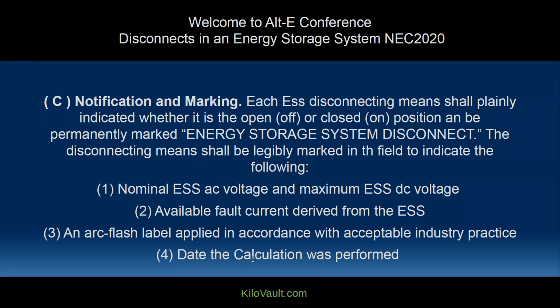And that's going to be not need to disconnect that point. If you have both, if you're over that 60 volts and under that 300 volts and no reference or no bond to ground, then you're going to need to have a disconnect on your positive and negative conductor at that time.